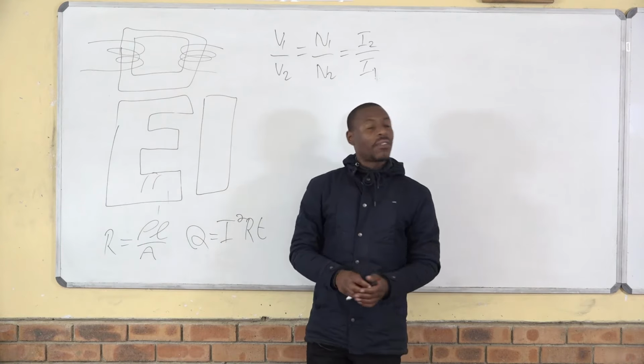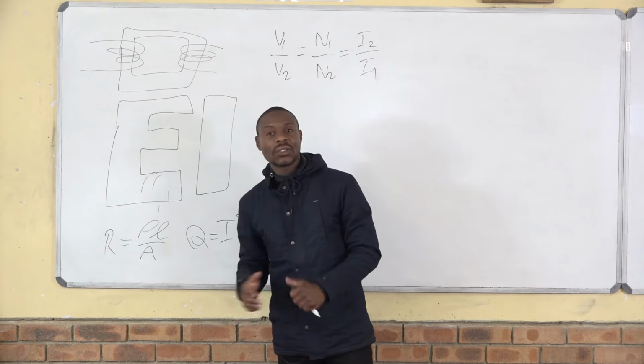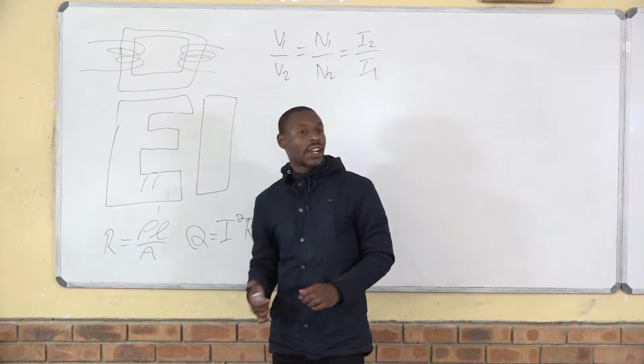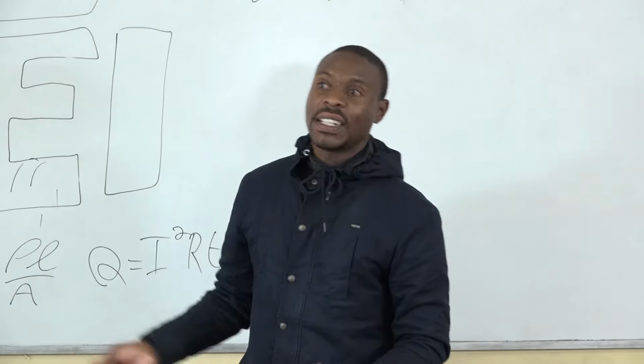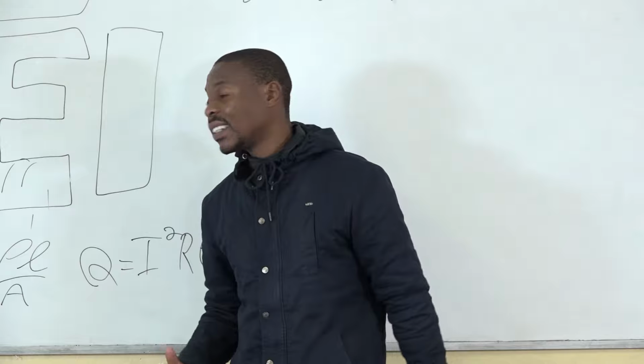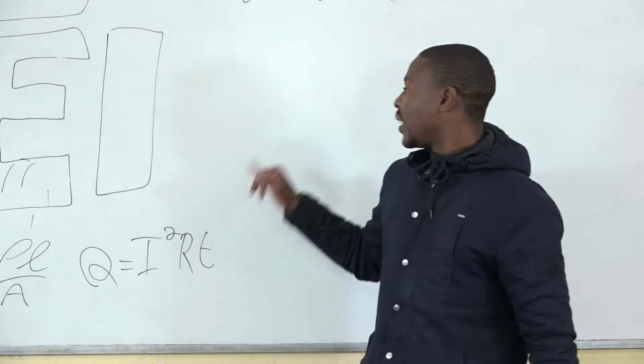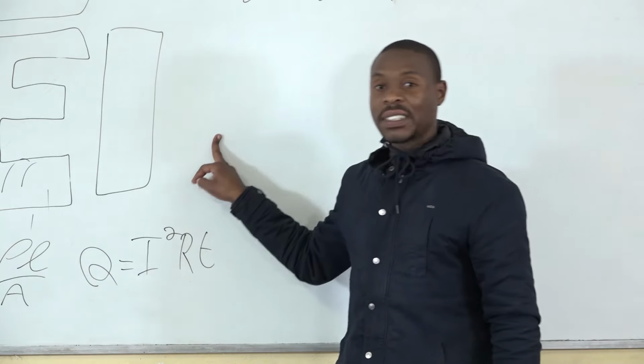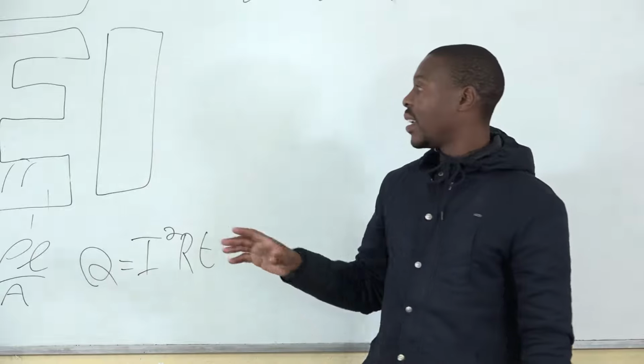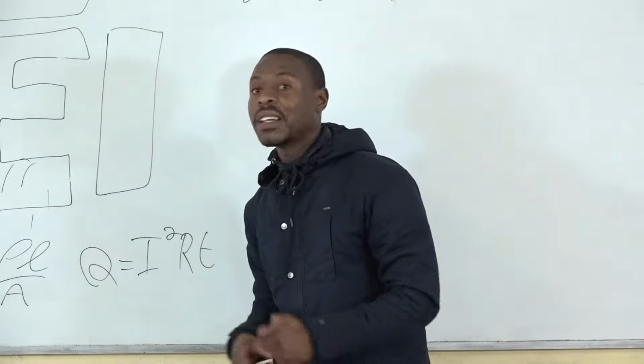Then you ask yourself, why is there no short circuit? Because this oil is a liquid. The reason for that, the oil also serves as an insulator, so it doesn't conduct electricity at all. So it has 2 functions. It serves as an insulator, it also cools down the temperature of the transformer.